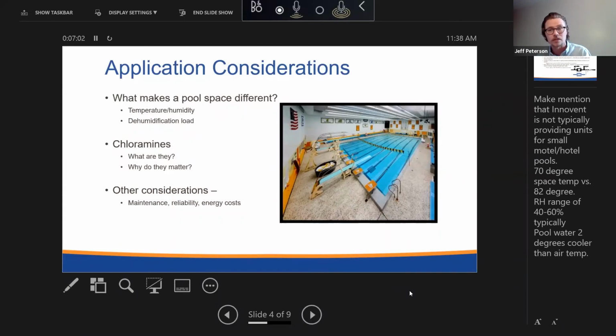However, chloramines are highly corrosive, and they're irritants for occupants. They can cause lung issues, they can cause irritation in eyes, and there are a lot of horror stories out there about chloramines building up to an excessive amount in pool spaces where there's not enough ventilation. When that happens, buildings can start falling apart structurally. And in some applications, there have been colleges and universities which aren't allowed to hold swim meets anymore because the chloramines have gotten so far out of whack.